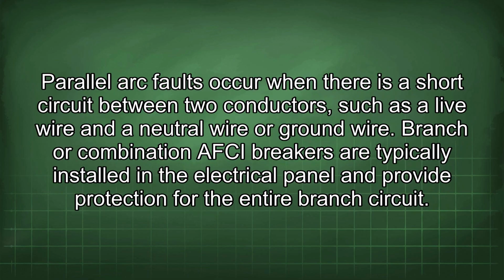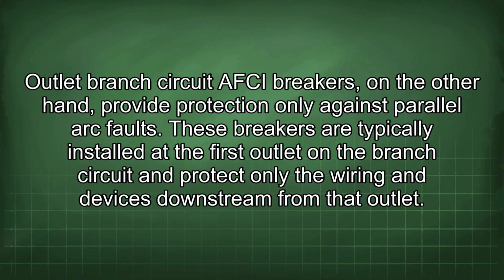Parallel arc faults occur when there is a short circuit between two conductors, such as a live wire and a neutral wire or ground wire. Branch or combination AFCI breakers are typically installed in the electrical panel and provide protection for the entire branch circuit. Outlet branch circuit AFCI breakers, on the other hand, provide protection only against parallel arc faults.